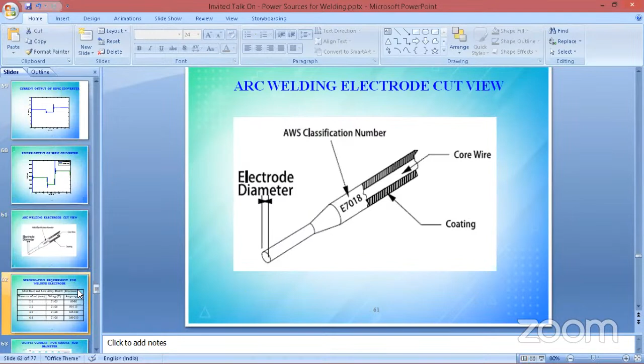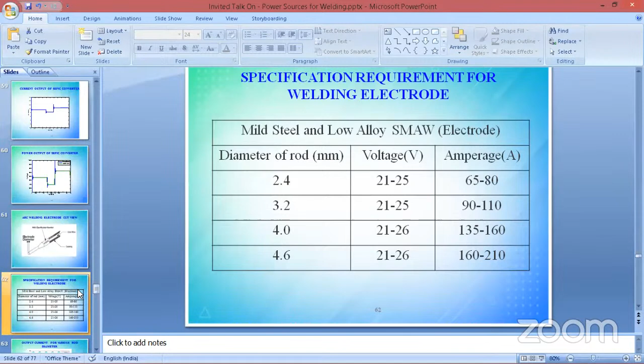The output voltage and current required for this electrode: voltage lies between 21 and 25, which we say is 24, and we try to produce this with the help of the cascaded converter. For a 2.4 size rod, the maximum current drawn is around 80 amps; for 3.2 it is 110; for 4 it is around 160; for 4.6 it is around 210.